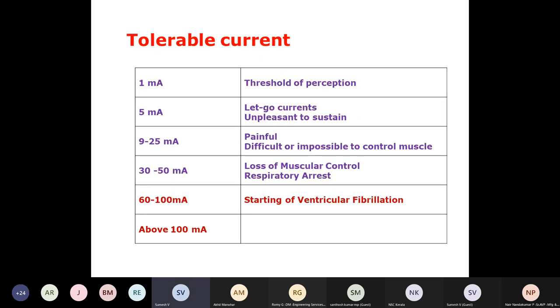Now, tolerable current. The IS says that a current of 1 milliampere to 4 milliampere close to a human body can be felt, but it does not cause any bad sensation. But 5 milliampere to 9 milliampere is called let go current. It gives some unpleasant sensation. Now 9 to 25 milliampere is painful. When a current of 9 to 25 milliampere flows, it is painful.